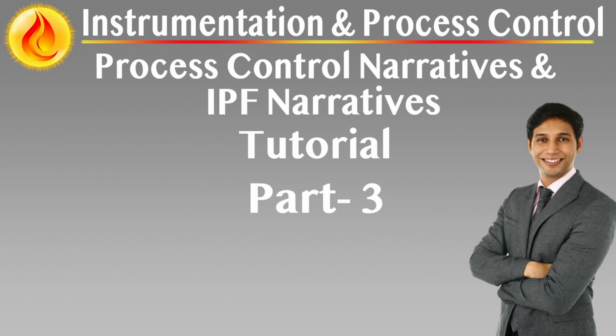This ensures that each IPF's trip path can be easily recognized and aligned with SIL documentation. Controller reinitializations. If controller reinitializations are implemented, for example, setting controllers to manual or forcing set points, they are grouped and distinguished using a different marker, e.g. I, to indicate these are not IPFs, but operator convenience functions.